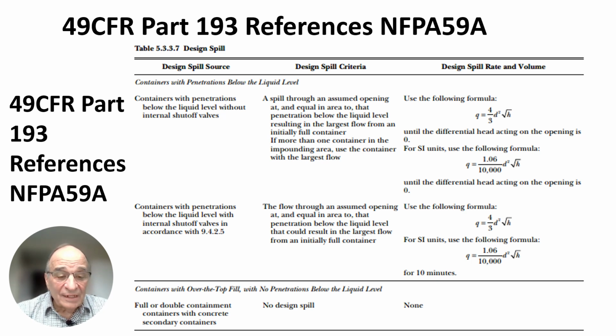And the third case is for a full or double containment tank. And for that, the design spill is zero. There is no design spill that you have to design for heat radiation calculations.